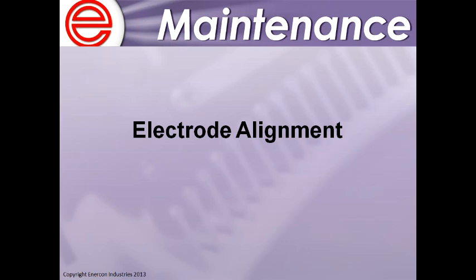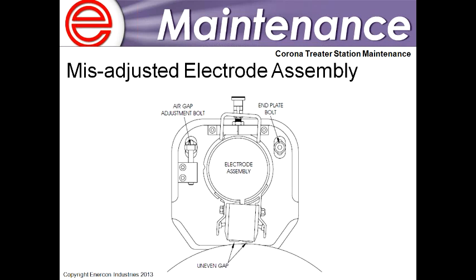And now we're just going to briefly talk about electrode alignment. I think it's fair to mention this, because anytime you do maintenance, we talk through the main guidelines of, number one, safety, lockout, tagout, then number two, doing the actual cleaning. Now, three, after you clean everything, since you were moving things around, it's not a bad idea to double check the electrode alignment. Assuming all the hardware was tight to begin with, you shouldn't need to readjust the gap, but since you were in there performing maintenance and cleaning, it's a good idea to re-verify it before you put it back into production.